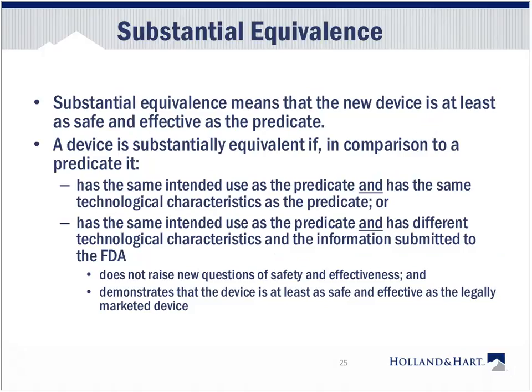So let's just talk about a very practical way in which this happens. You have a device that used analog technology. The new device is used for the exact same purpose but now uses digital. The FDA does not have a problem with that. It says that we know enough about digital technology now that the new technology in the new device will still make it substantially equivalent to the predicate device.